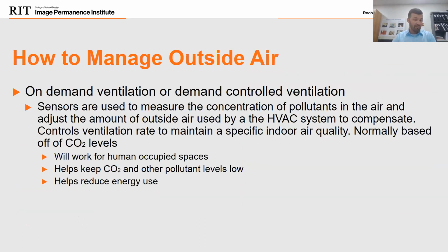Manage your outside air a little bit better. Some energy efficiency measures are, if you can't really shut off the outside air, which we never would recommend, just kind of reducing that consumption. But if you're concerned about that consumption reduction, especially for galleries or so, can you reduce it to on-demand ventilation or demand controlled, where you're having a CO2 sensor that is tied to the actuator for the damper. So if conditions get to a certain point, the CO2 sensor will open the dampers and let more outside air into the space.